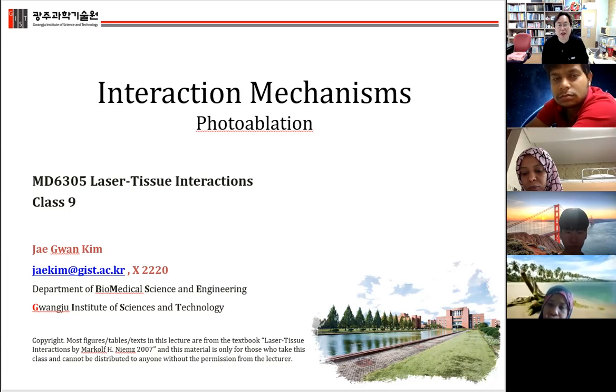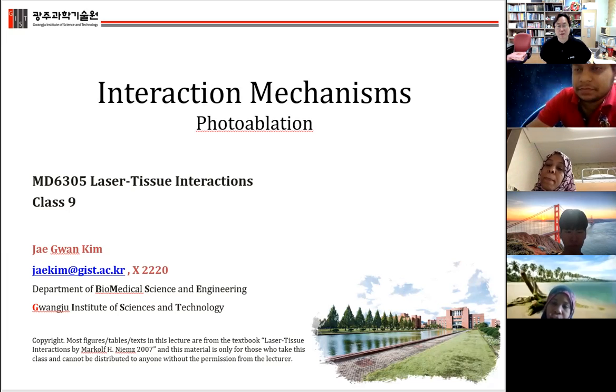But here later you will see that it has a name of the photoablation because you need to have a specific wavelength and also a specific duration time for the laser to do the photoablation. So in the photoablation, important thing is that the energy that photon has versus the binding energy of the molecules in the tissue. So if the photon energy is higher than the binding energy between each molecule, then you can cause the photoablation. But if not, then it may not actually do any ablation.